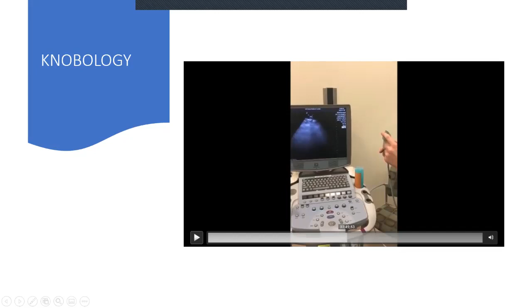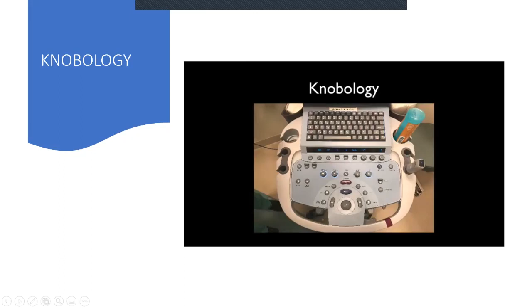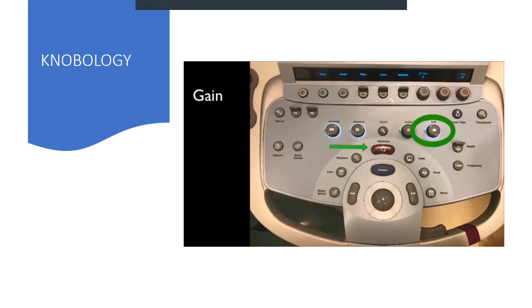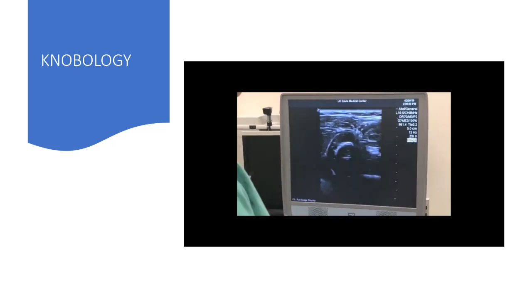Sorry, I just want to come back to this. So this is the crux of what we're going to talk about now. And these are the different functions that you find on your machine. Let me just get that started again. Controls of the ultrasound machine and where to find them, also known as knobology. Gain. This is a function in B mode or 2D mode, which is normally the default mode. The gain is the degree of amplification of the returning signal, and adjusting it increases or decreases the overall brightness.